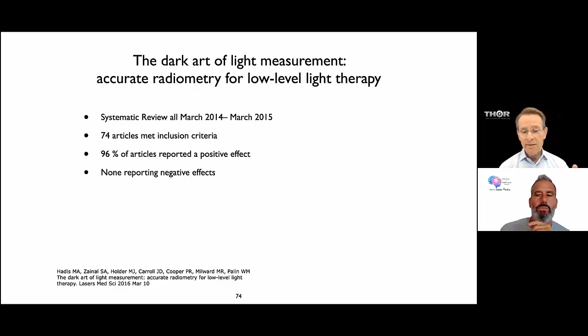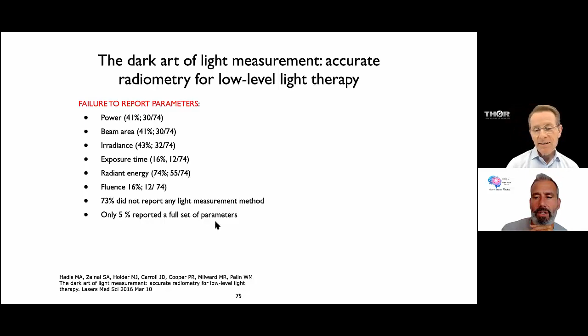41% of papers in that 12-month period failed to report the power, 41% failed to report beam area, 43% didn't report the irradiance, 16% didn't even say how long they treated for. The total energy, that's the joules, 74% didn't report that. The fluence, the joules per centimeter squared, 16% didn't report that. 73% did not report testing the device with anything. Only 5% of papers in that period actually reported a full set of parameters. So that is a dark spot.